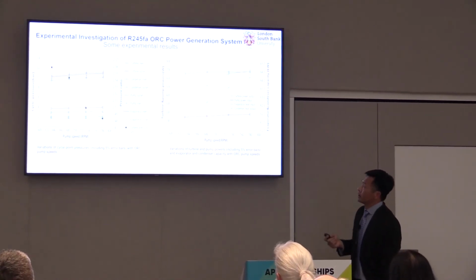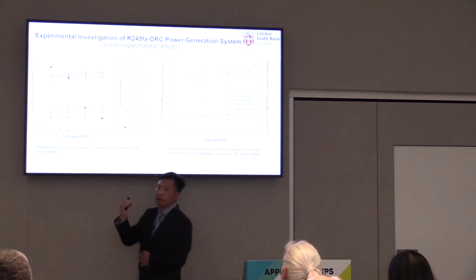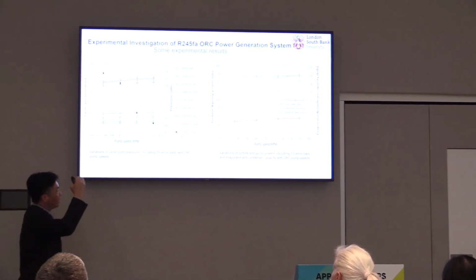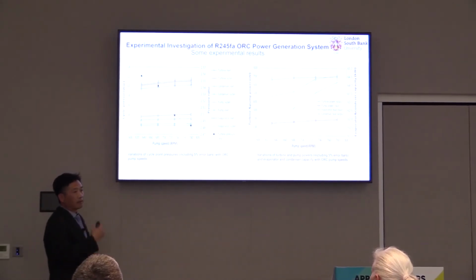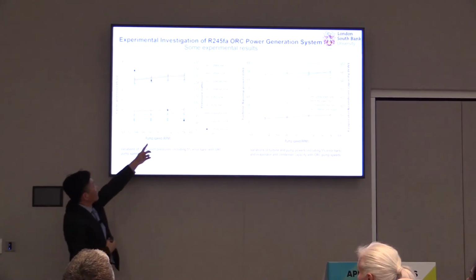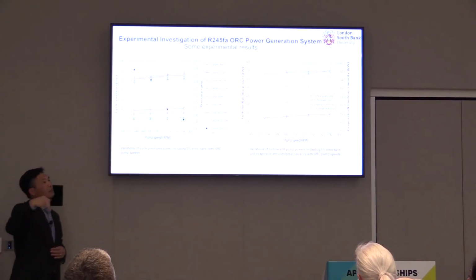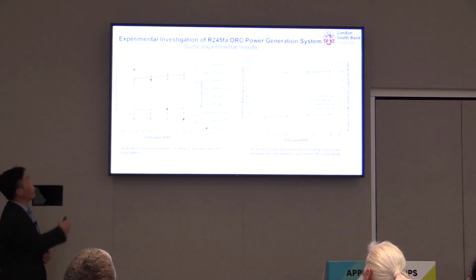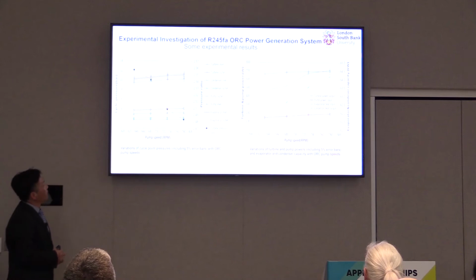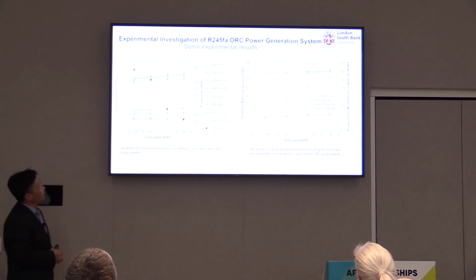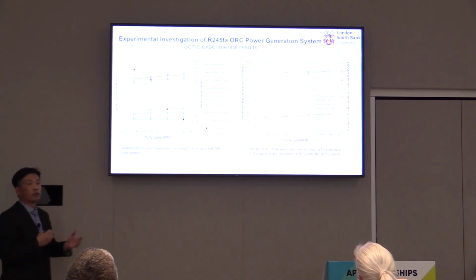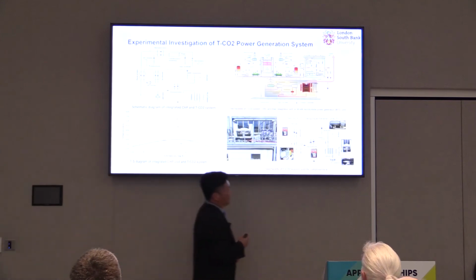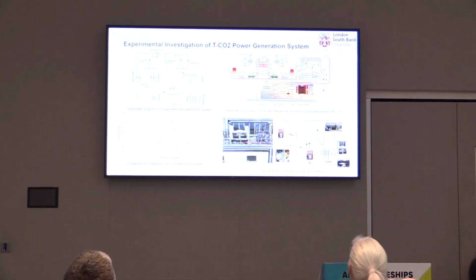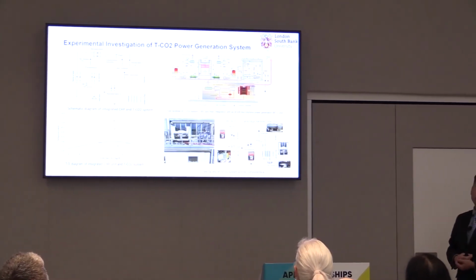You can see that when you increase the pump speed, the high side organic Rankine cycle pressure will increase, and in the meantime the low pressure side pressure will increase as well. The pressure increase on the low pressure side is larger than on the high pressure side. That's why the pressure ratio will decrease with an increase of the pump speed. So from here, you can also create a function so that you can control the ORC pressure by modulating the pump speed. Now the tri-generation system, you see the working fluid is different.